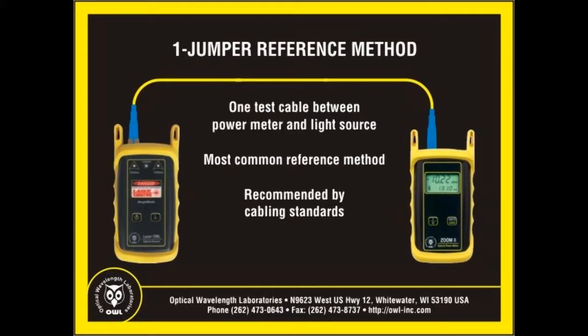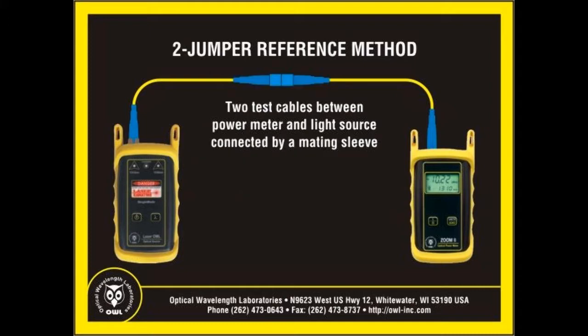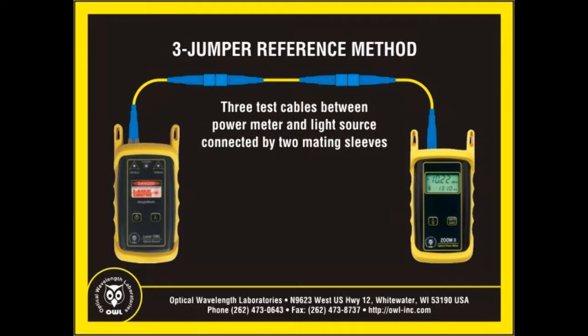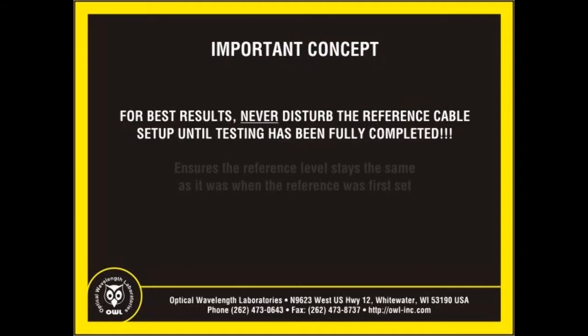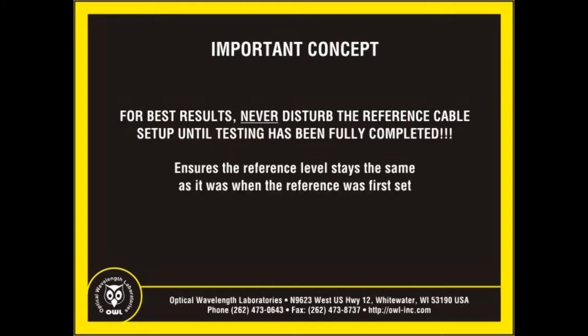The most common reference method is the one-jumper method, where one patch cable is inserted between the power meter and the light source. This method has become the recommended reference method in recent years. The two-jumper method uses two test cables, one for each tester, with a mating sleeve in the middle. The three-jumper method adds a third test cable and a second mating sleeve, where a third cable is inserted between the two reference cables attached to the testers. This is the least common of the three reference methods. For best results, never disturb the reference cable setup until testing has been fully completed. This ensures that the reference power coming out of the light source is the same as when the reference power was recorded in the power meter.